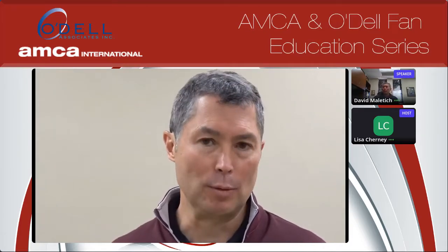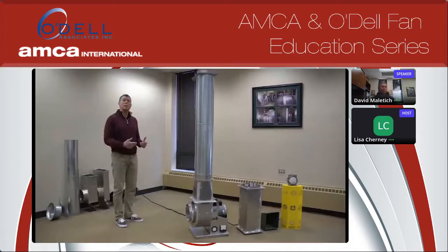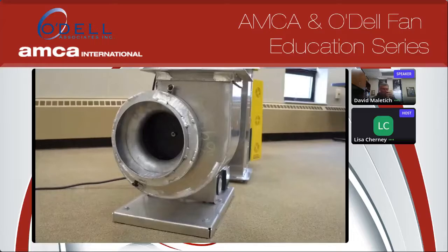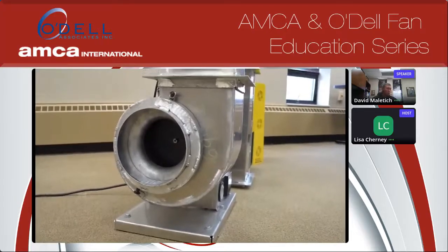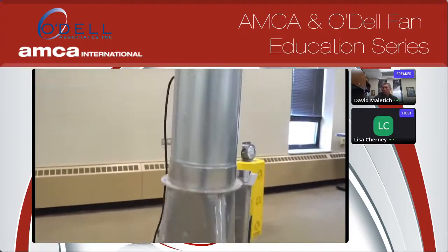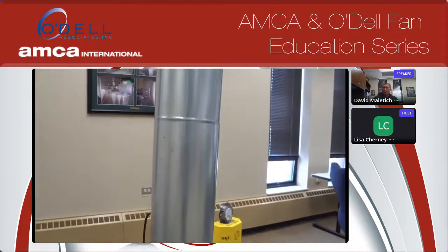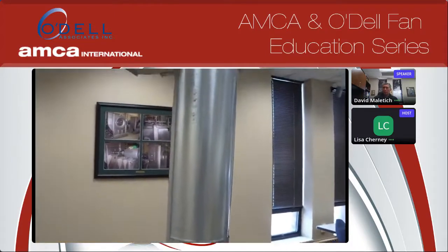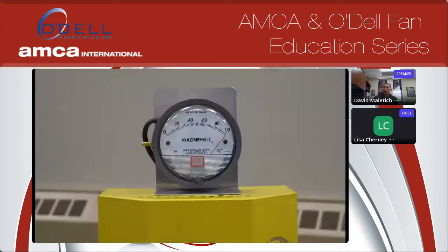Before we get started, let me just explain a little bit about how this fan is configured. First, the fan has an open inlet that allows the air to uniformly load the wheel, and we have a straight run of ductwork just as the fan gets tested at AMCA to allow for the static pressure to regain before it goes out to atmosphere.